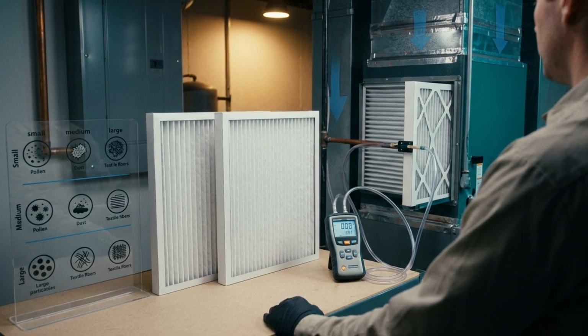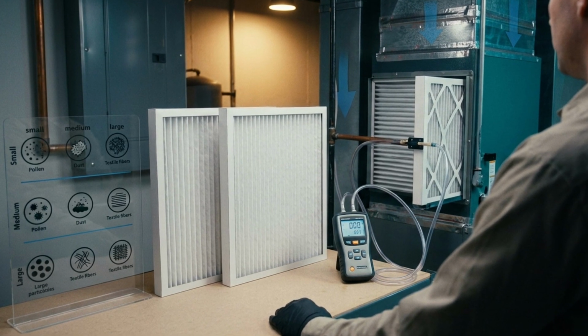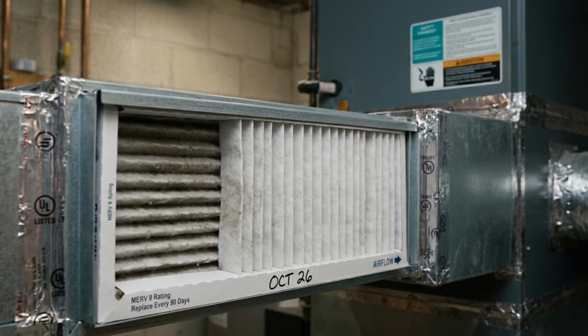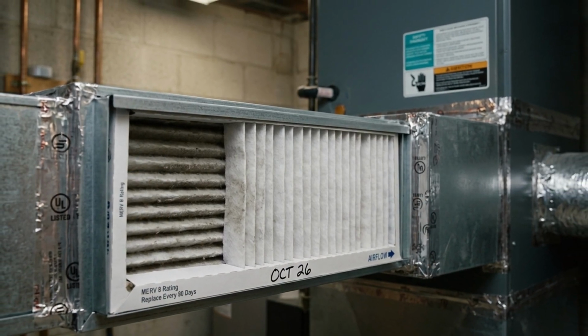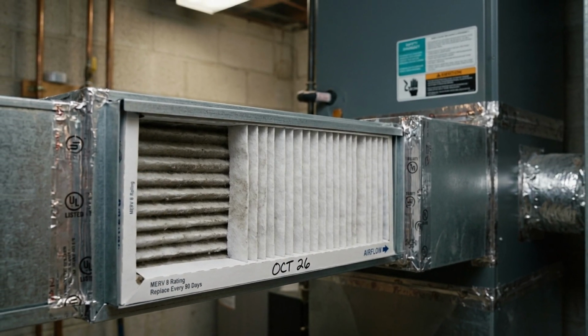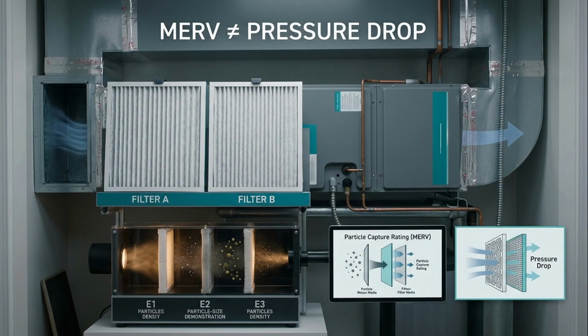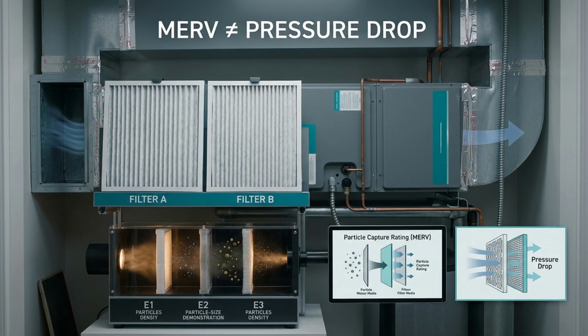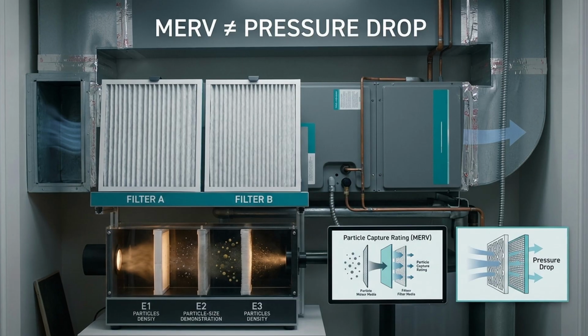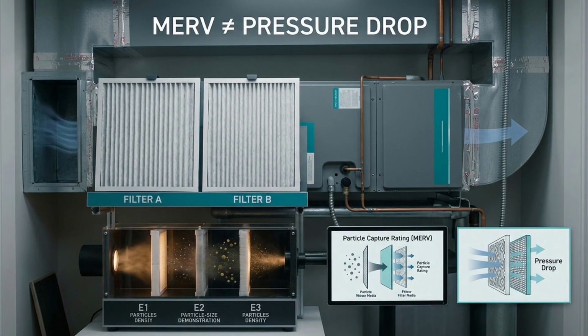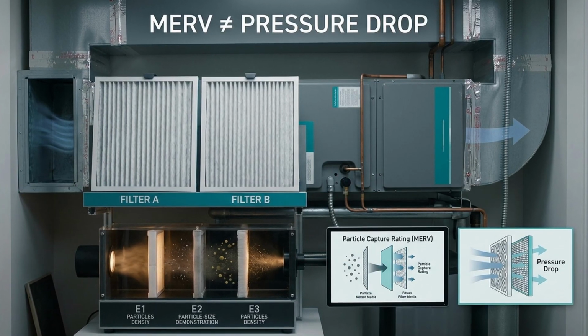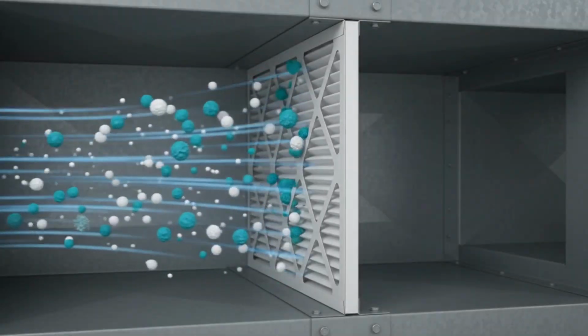How efficiently does this filter capture particles passing through it? And how much resistance does this exact filter add when air moves through this exact system? MERV helps answer the first question. It is a standardized way to describe particle capture performance across a range of particle sizes. MERV is not a direct pressure drop rating for every filter carrying that number.